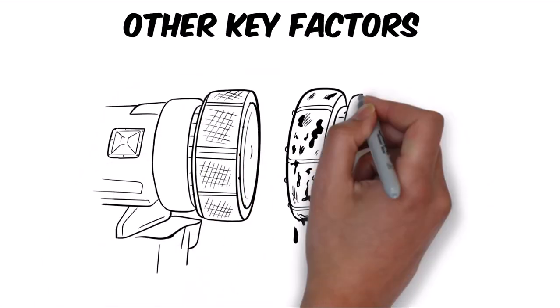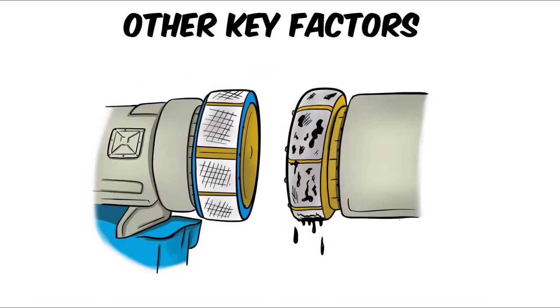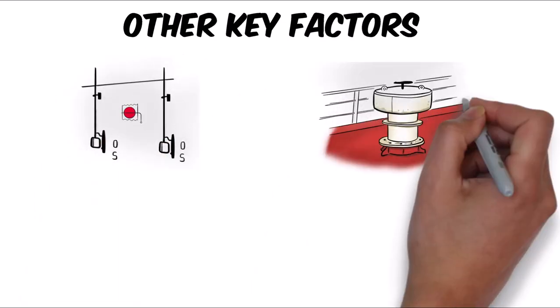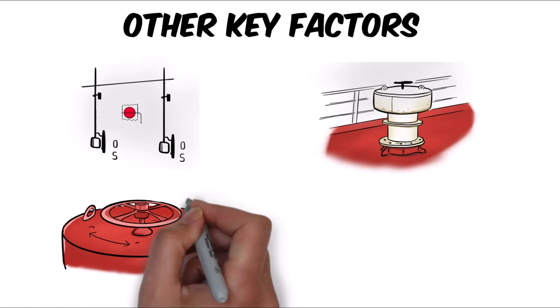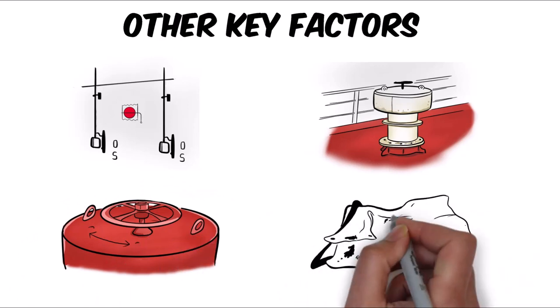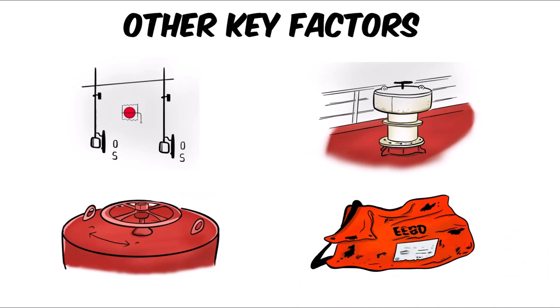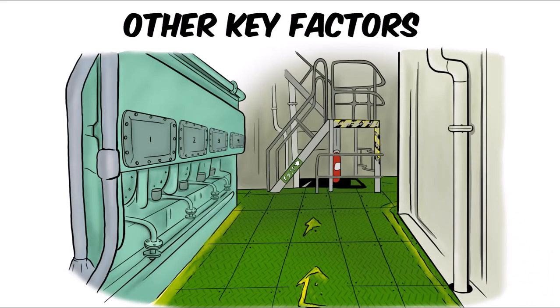Air filters are made of flammable material or soaked with oil. Inoperative fire dampers and shutters. Space served not marked. Open closed position marking faded or unreadable. Poorly serviced or wrongly positioned emergency escape breathing devices. Fire escape routes and exits are not marked clearly.